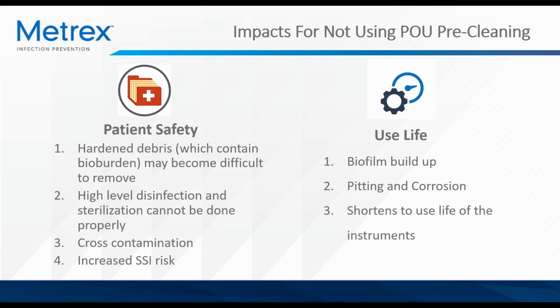On the flip side, there's also the concern for use life of the medical instrumentation. Lack of point of use pre-cleaning allows biofilm to build up on instrumentation. This can lead to pitting and corrosion of the instrument surfaces, like we saw in those photos. This shortens the use life of said instruments. So an expensive medical instrument that was supposed to last 5 years now has to be replaced after 6 months because it's showing signs of misuse or improper reprocessing.